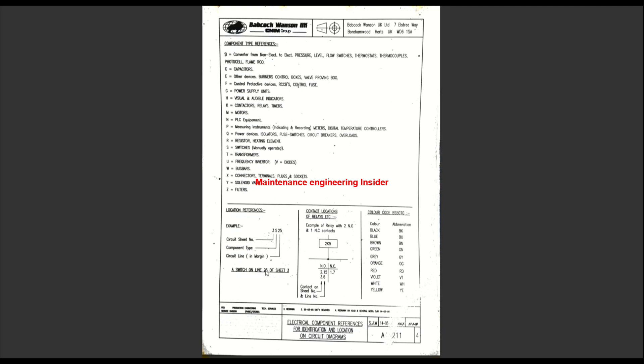Anywhere you see the coil of a relay or a contactor, it tells you where you can find the contacts related to that relay. It's telling you this coil is associated with two normally open contacts and one normally closed contact. One can be found on sheet three, line six, and the normally closed contact can be found on sheet one, line seven.